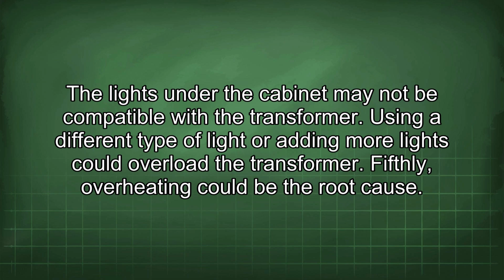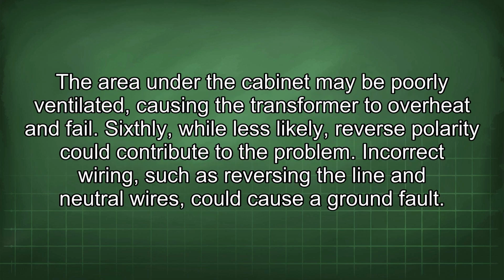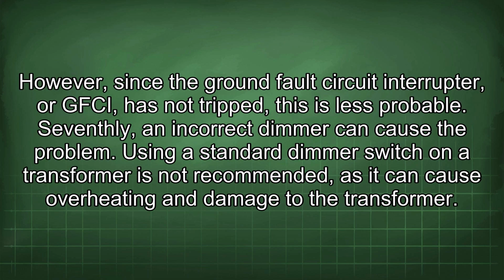Fifthly, overheating could be the root cause. The area under the cabinet may be poorly ventilated, causing the transformer to overheat and fail. Sixthly, while less likely, reverse polarity could contribute to the problem. Incorrect wiring, such as reversing the line and neutral wires, could cause a ground fault. However, since the ground fault circuit interrupter, or GFCI, has not tripped, this is less probable.